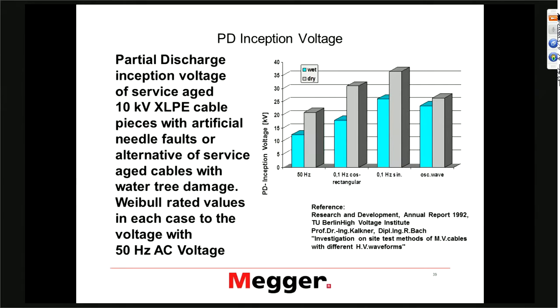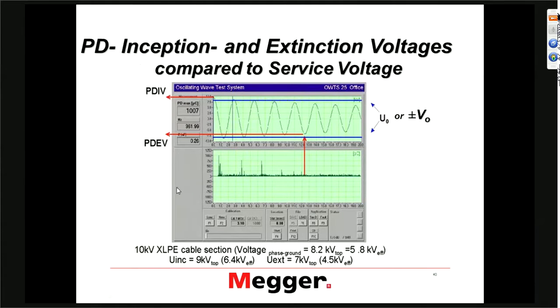PD testing at power frequency is today very common, but also PD testing at 0.1 Hz — there is nothing wrong with 0.1 Hz PD testing. However, results might be different when looking at splices and terminations, because the inception voltage might be higher than at operating voltage. When you go to power frequency, these issues can be avoided. Our recommendation is to do partial discharge testing at power frequency.